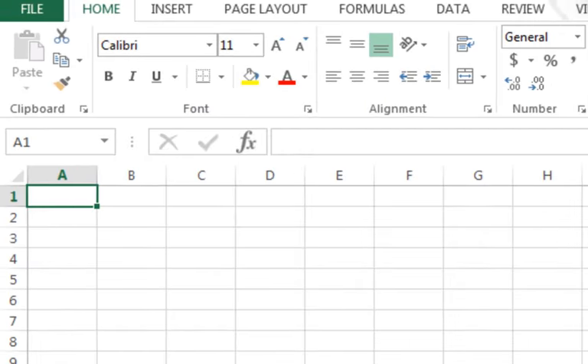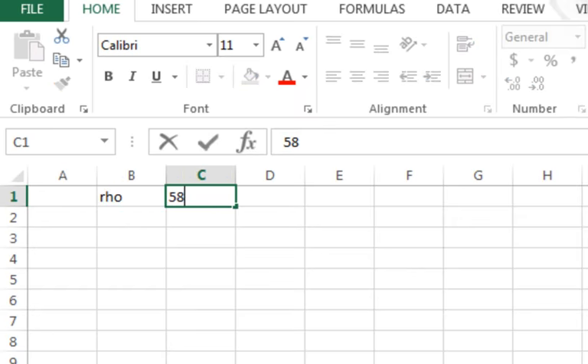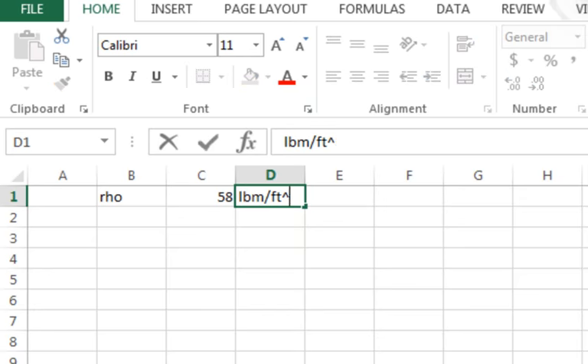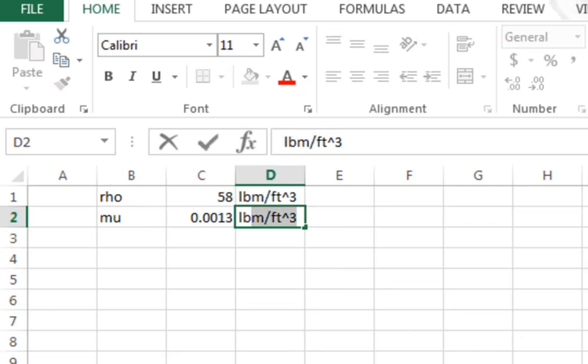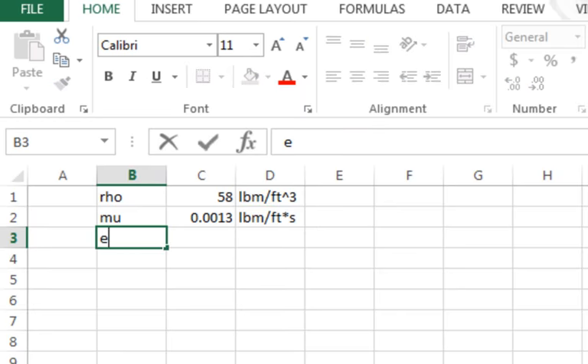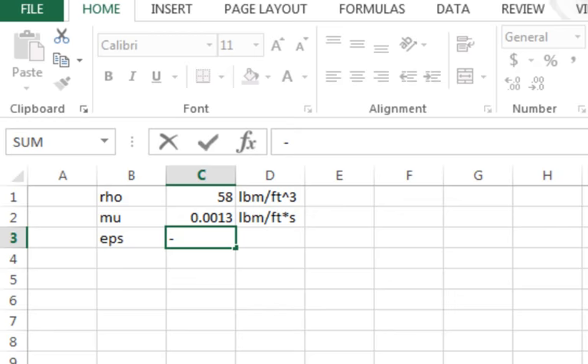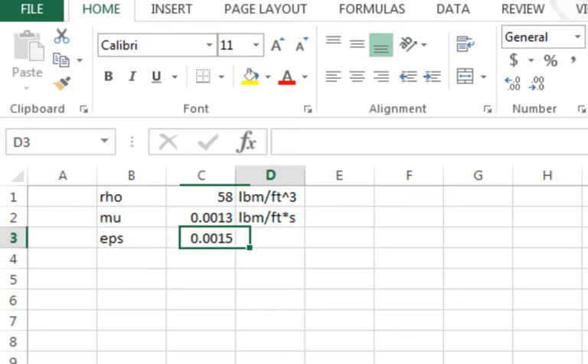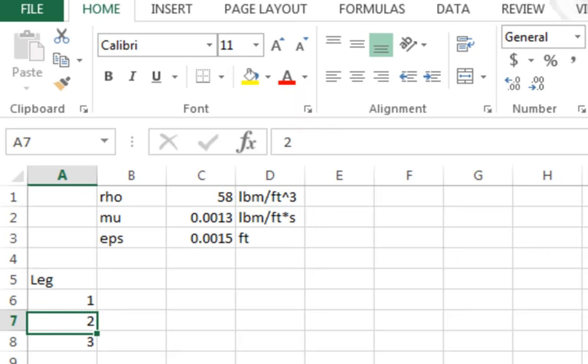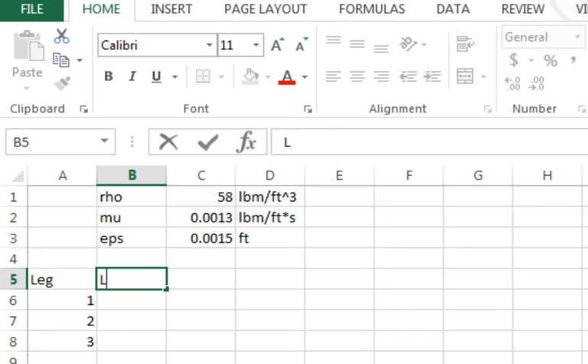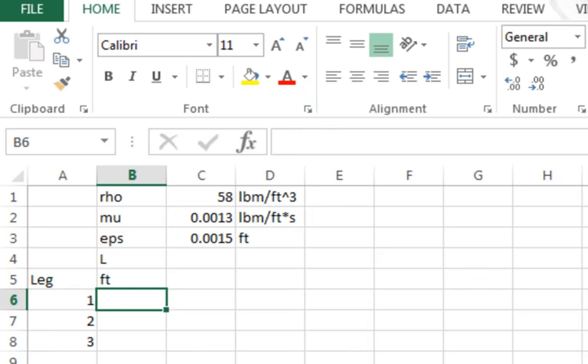In Excel, I'll enter density: RHO = 58 lbm per cubic foot. Viscosity mu = 0.0013 lbm per foot-second. Roughness epsilon for steel pipe = 0.0015 feet. Then I set up Leg 1, Leg 2, Leg 3 with their lengths: Leg 1 = 300 ft, Leg 2 = 150 ft, Leg 3 = 200 ft.